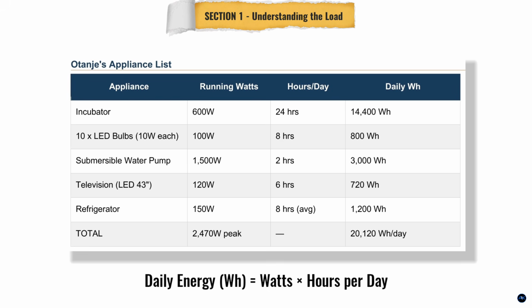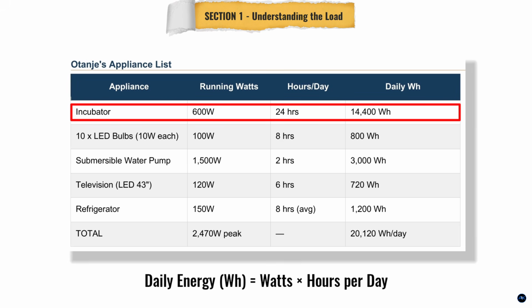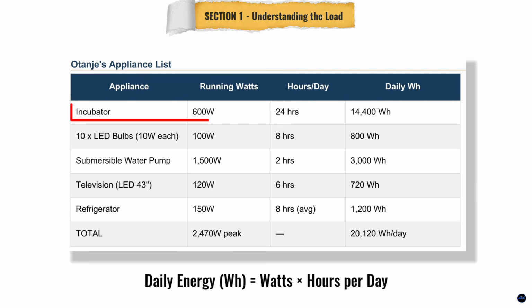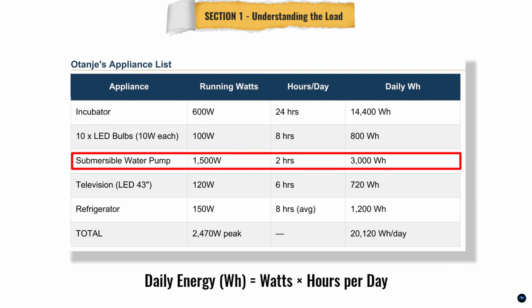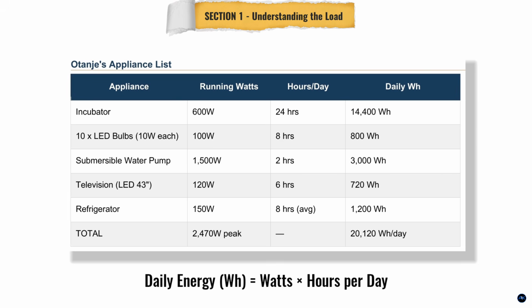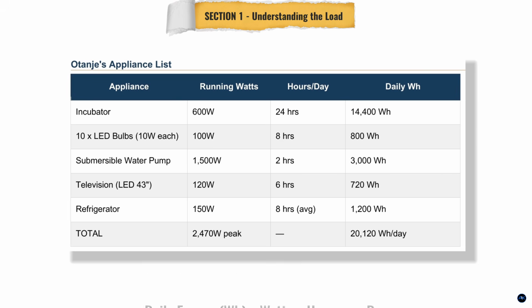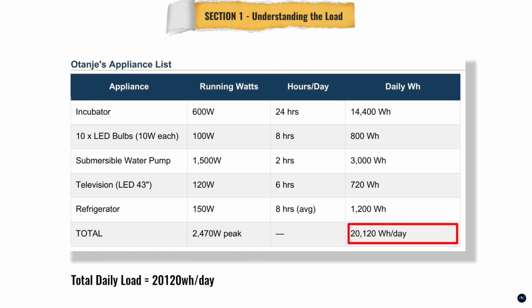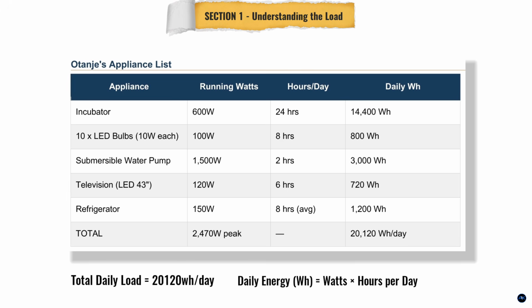But peak watts alone don't tell the whole story. We need to know how many hours each appliance runs per day. The incubator runs 24 hours, that is 14,400 watt-hours per day. The pump runs just 2 hours, but at 1,500 watts, that is still 3,000 watt-hours. Add everything together and we get 20,120 watt-hours, or about 20 kilowatt-hours every single day.